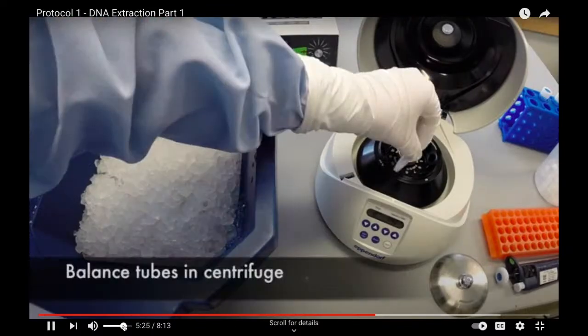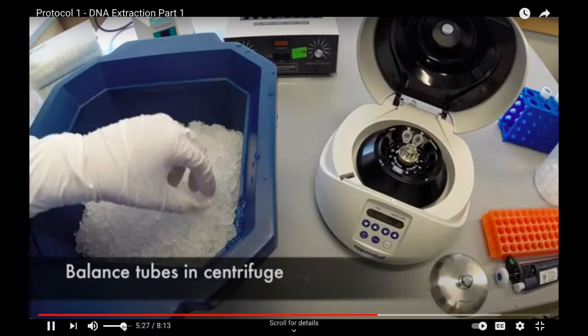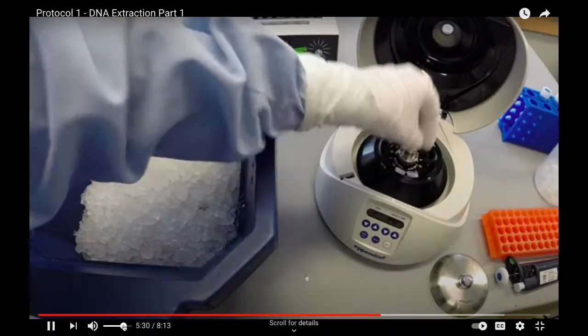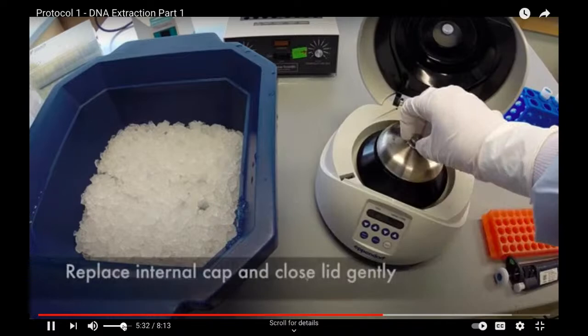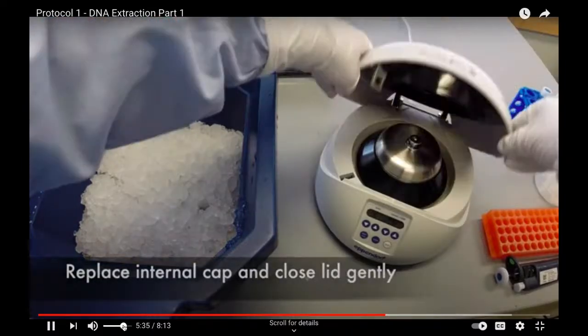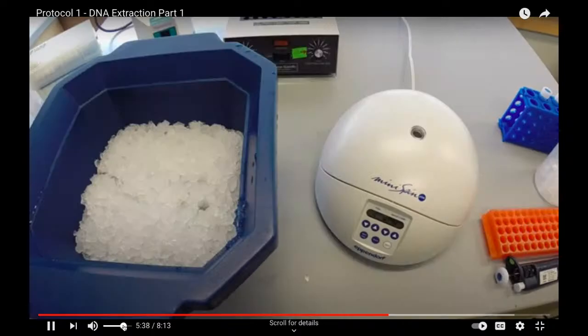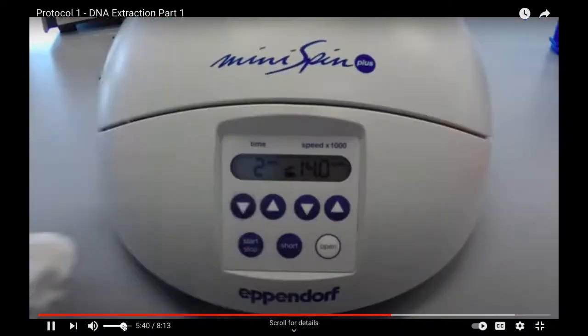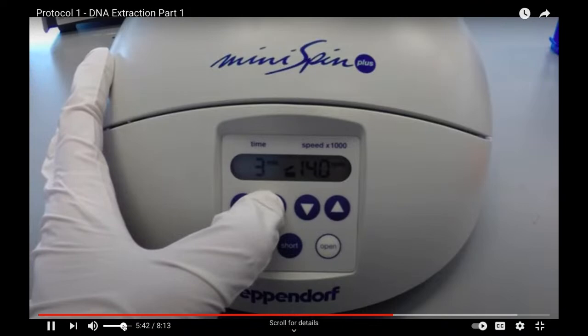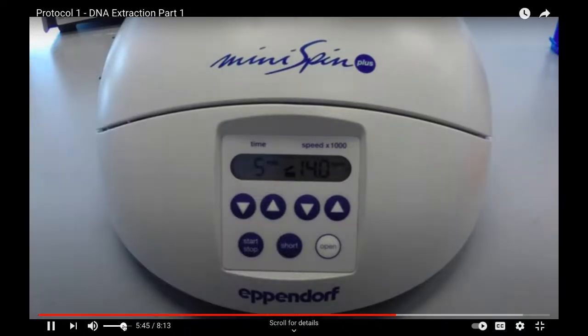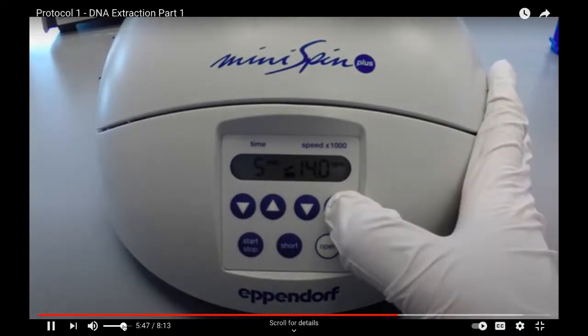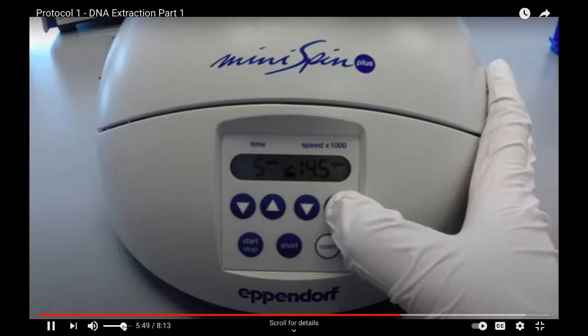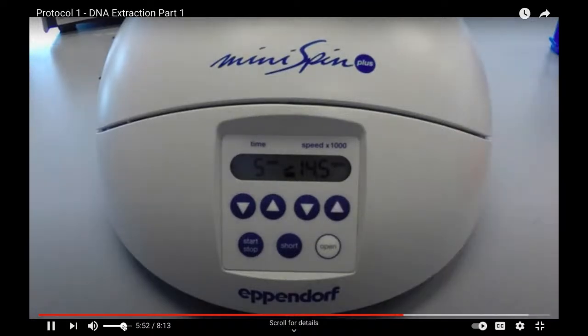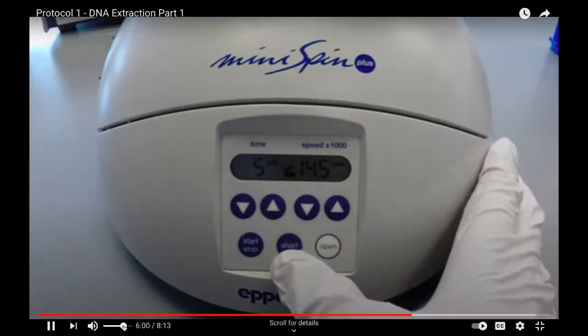And balance the tubes across the rotor by ensuring that all tubes have equal volumes. Replace the metal lid and press it until it clicks securely onto the rotor. Close the lid to the microcentrifuge gently. Change the centrifugation time by pressing the arrows to the desired time, in this case 5 minutes. Press the arrows by the speed to navigate to the proper RPM. In this case 14.5 thousand RPM is the max this centrifuge can perform and is close enough to our desired speed. Press the start button.